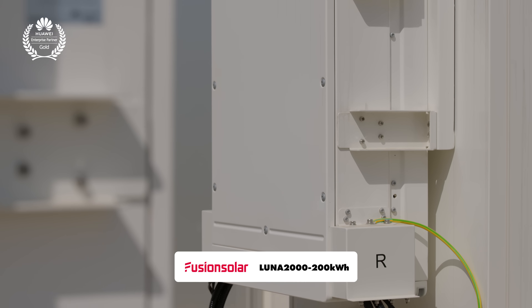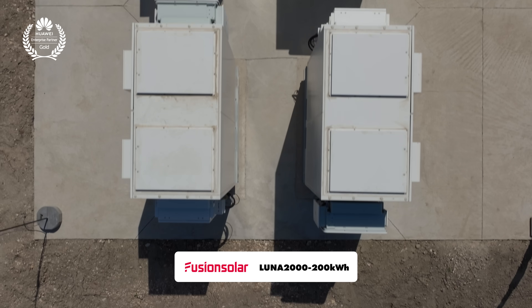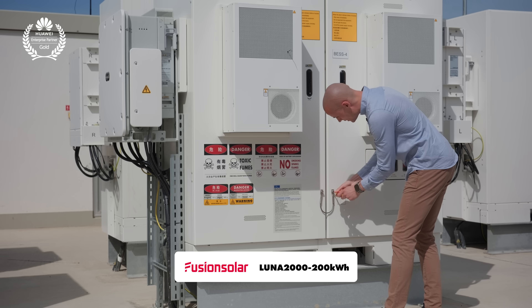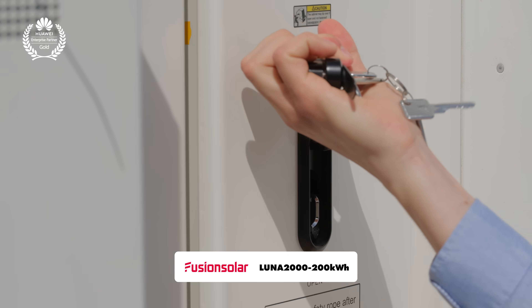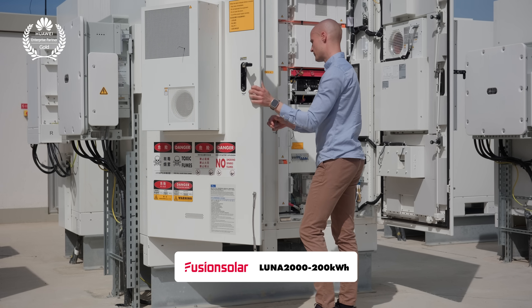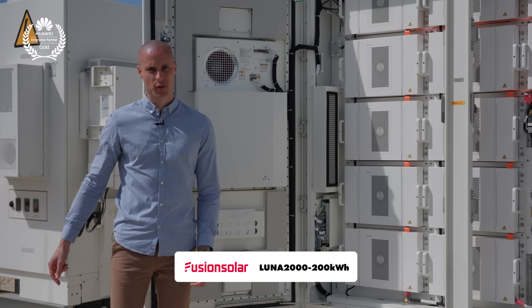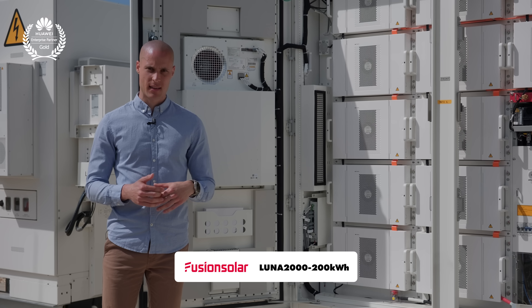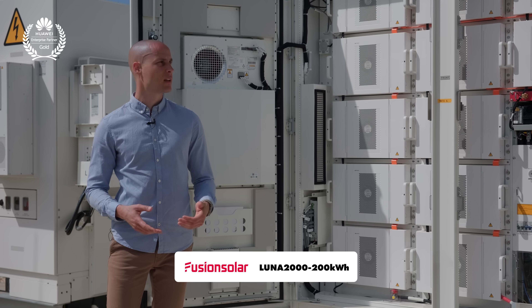To open a cabinet like this — fully operational and securely locked — it's not just turning the handle and pulling it open. It requires a process to ensure safety and prevent access considering the electrical hazards inside. The converter immediately clicked into action when the door was opened, detecting it and stopping production right away. This safety feature ensures that no parts remain energized that could cause electric shock or pose other hazards.